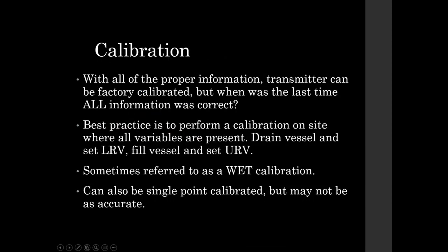Calibration, pretty straightforward. This applies not only to these ultrasonics, but as well as radars here. With all the proper information, the transmitter can be factory calibrated off a data sheet, for example. But when was the last time that the data sheet and the field actually matched up properly? So that's something to be aware of. Even though your data sheet says the vessel is this big and the nozzles are here and there, you want to make sure that you verify that.